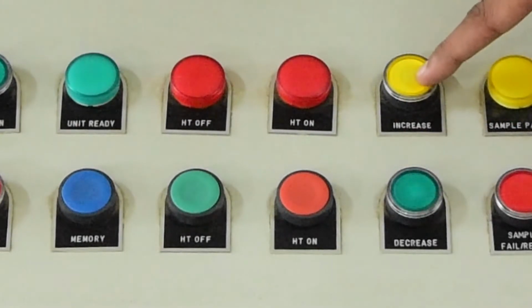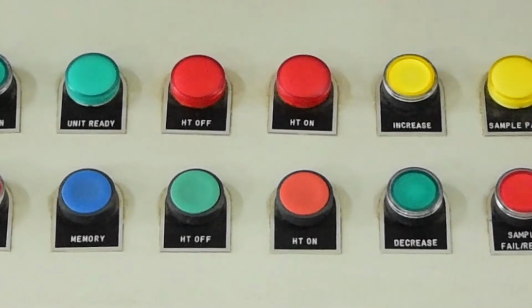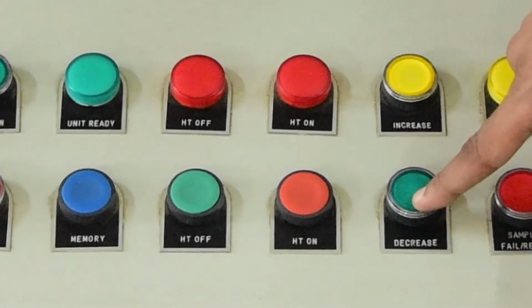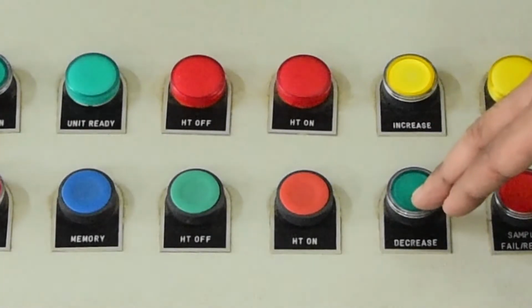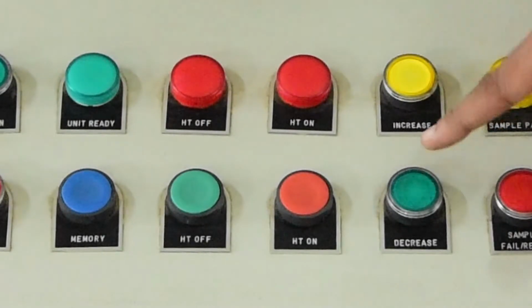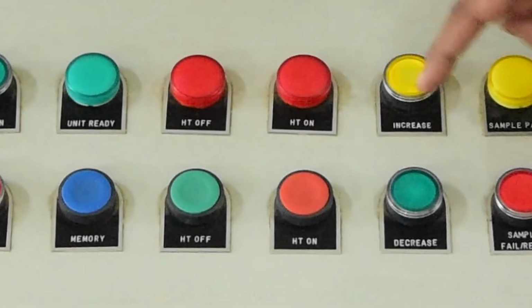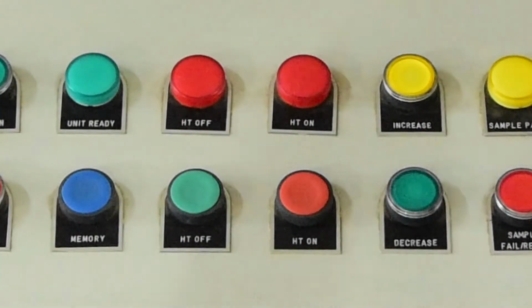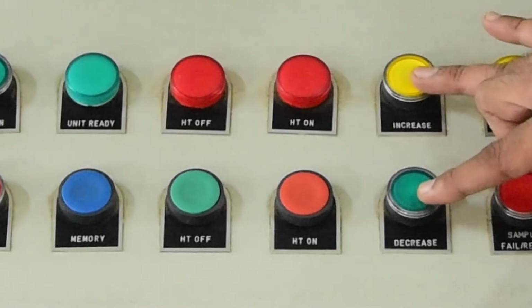So this is a motorized control. A low voltage variac is present under this control panel. It sets the primary voltage, the excitation voltage, of the cascade transformers. So as we increase this voltage, the transformer output will also increase. This is a decrease button. So we decrease the input side or primary side low voltage of the transformer. There is a tap changing control which is a motorized one. By pressing this switch, we actually adjust the position of a motorized tap changer on the input side of the cascade transformers. So the voltage applied to the cascade transformer through a variac available inside this control panel can be adjusted by using these two switches.